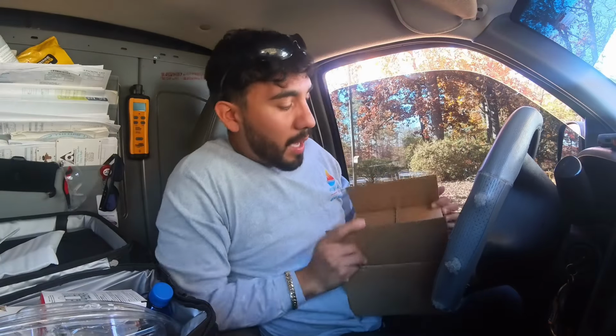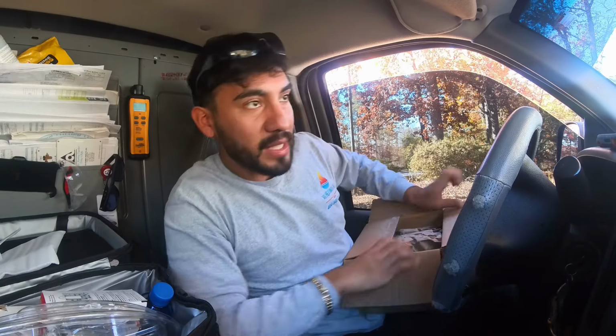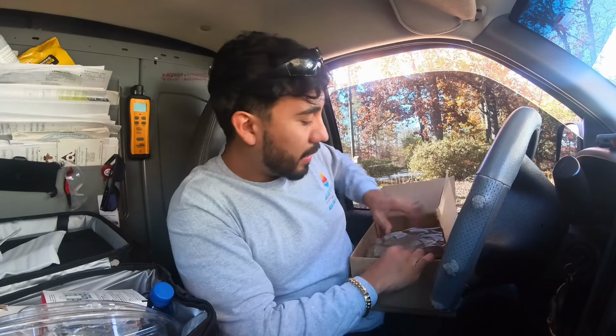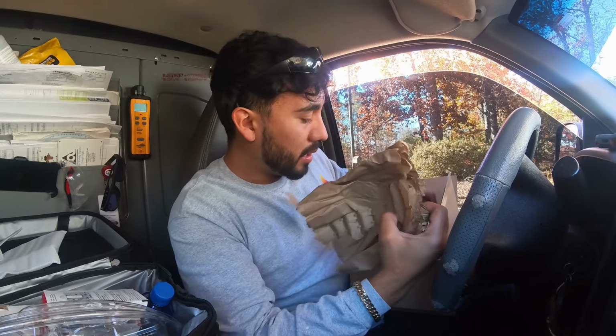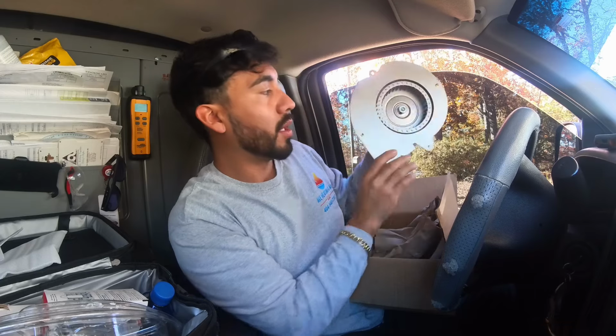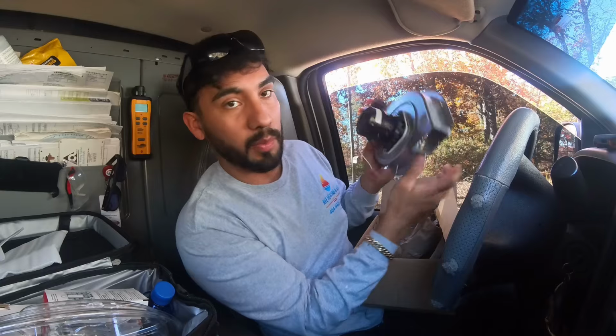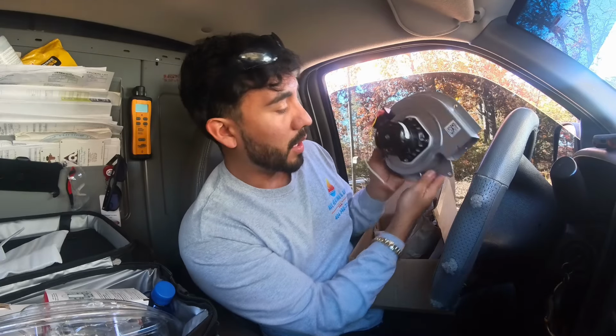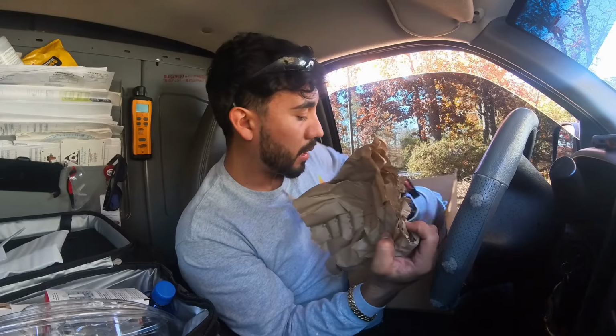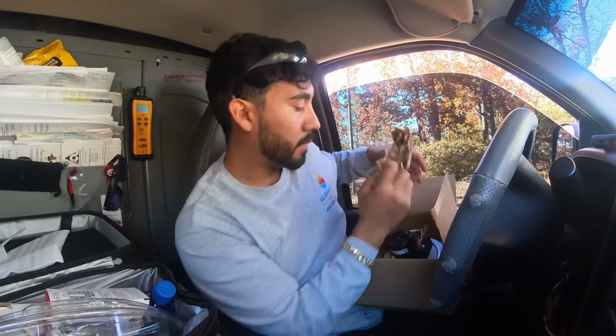I also got the inducer right here as well, and we already set up the thermostat for it to lock out at 40 degrees on heat pump. After 40 degrees, our secondary heat, which is gas in this case, is gonna come on. The issue was that our inducer was broke, so we got it right here, guys. Let's see what we could do.